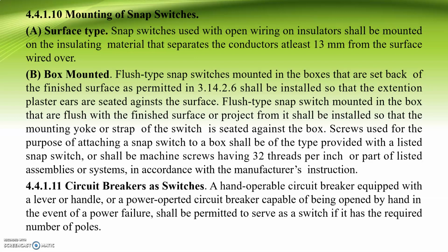So chapter 4.4.1.10, mounting of snap switches. So first is the surface type. So snap switches used with open wiring or on insulators shall be mounted on insulating material that separates the conductors at least 13 mm from the surface wired over.